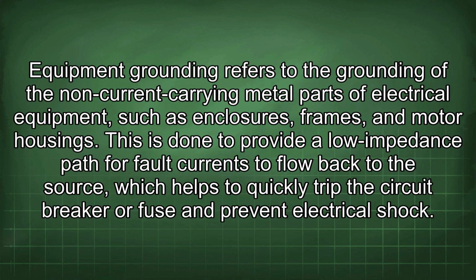Equipment grounding refers to the grounding of the non-current carrying metal parts of electrical equipment, such as enclosures, frames, and motor housings. This is done to provide a low impedance path for fault currents to flow back to the source, which helps to quickly trip the circuit breaker or fuse and prevent electrical shock.